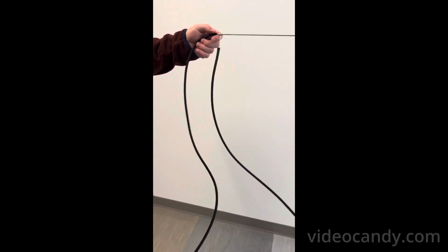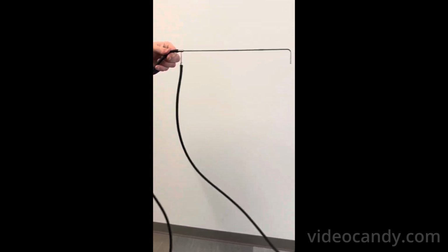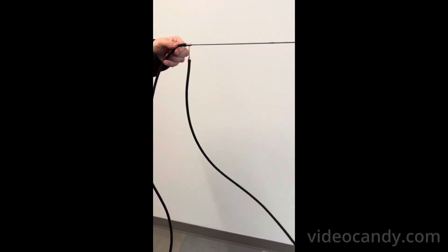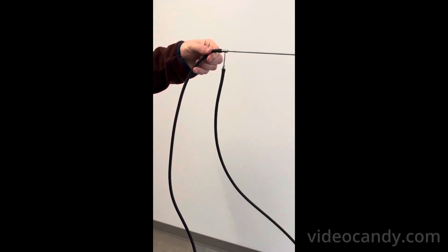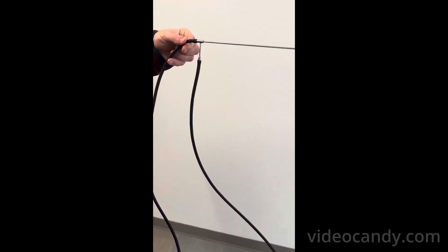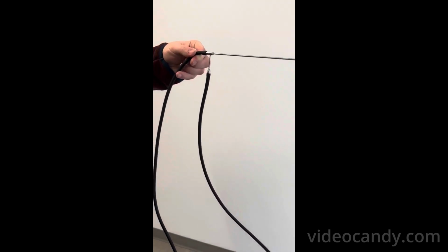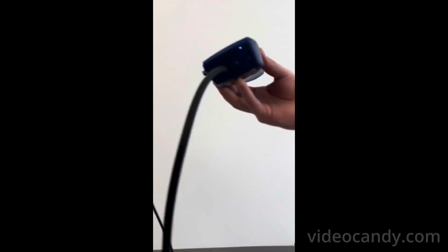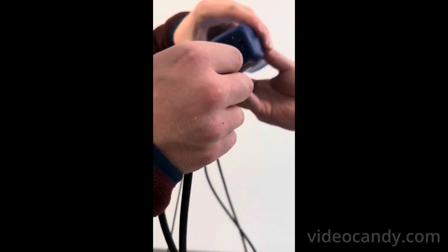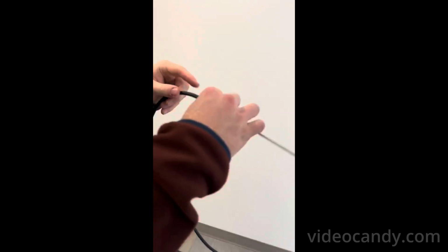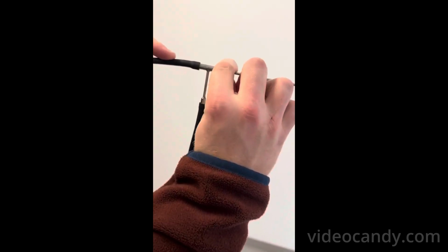In order to take a velocity pressure measurement, you are going to want both tubes connected to the sides of the pitot tube. The negative part of your device is going to be connected to the wall measurement of the pitot tube, and then the positive terminal is going to be connected to the inside tube of the pitot tube, just like this.